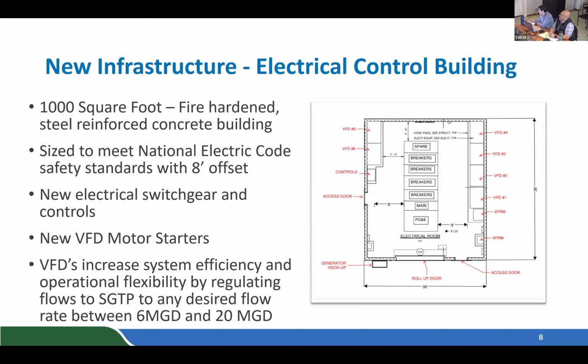The length of the building's going to remain the same, but the building is going to get a little bit wider, so that way we could have the required safety offsets. And this will house all the new electrical switchgear. So you have your new PG&E meter, the main breaker, and all the breakers for the pumps. And within that, you'll get the VFD motor starters, and they're kind of laid throughout the perimeter of the building. And then you'll have our controls box.